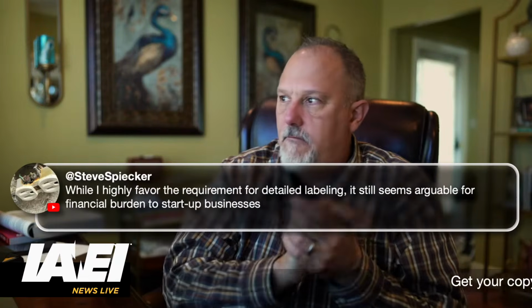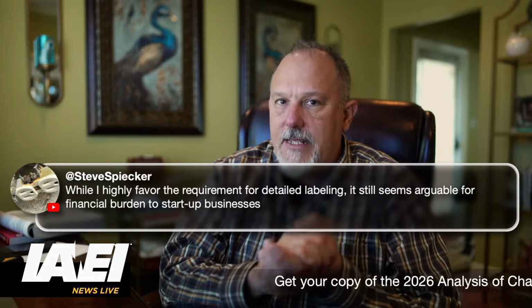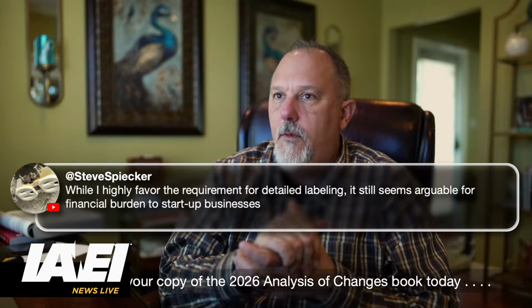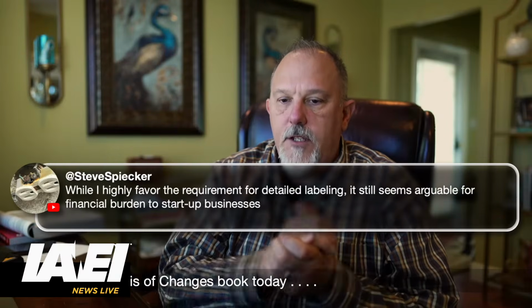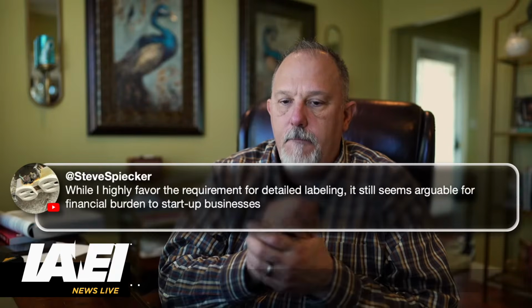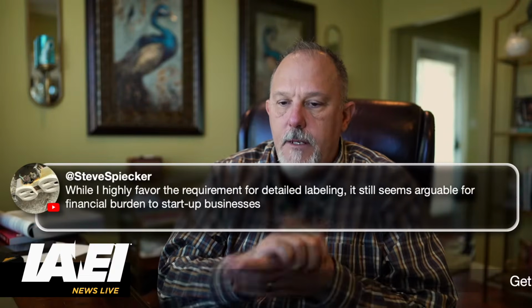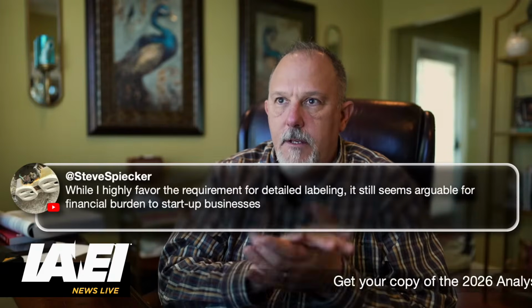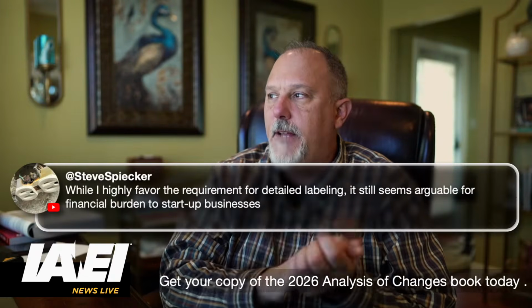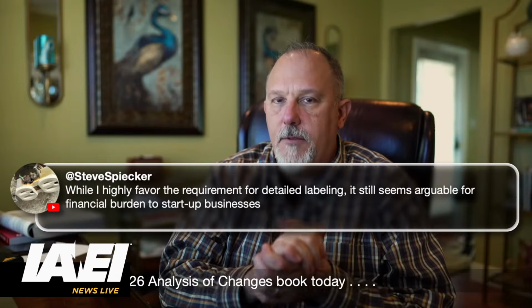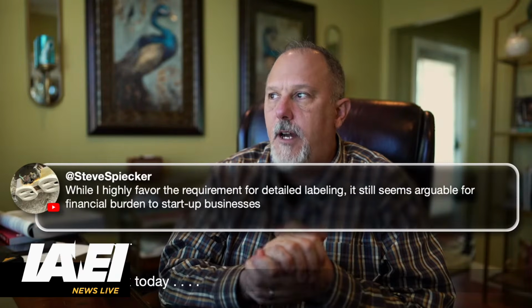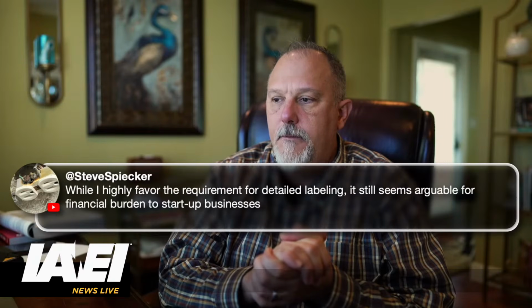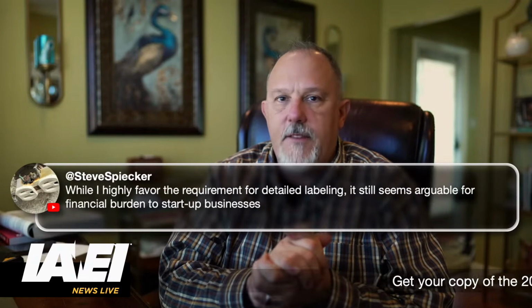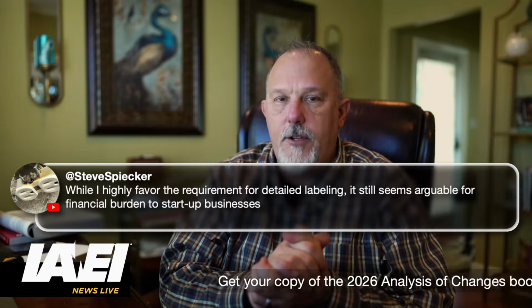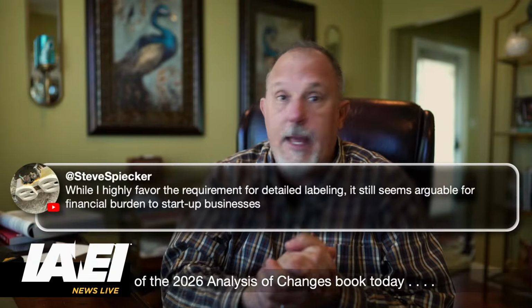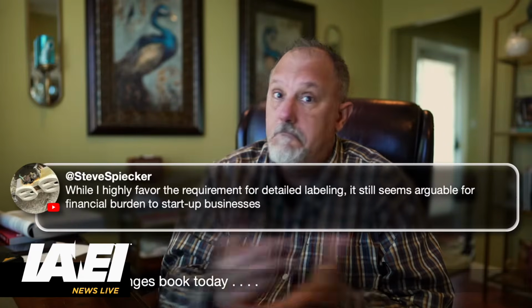How do I say this? NFPA 70E is an OSHA requirement. I don't know how to say it, but if you own a building, a structure, and you're going to energize it, other than a dwelling unit, somehow you have got to address the OSHA requirements. I mean, you could try the PPE category method, which could be used to label the equipment. Right?